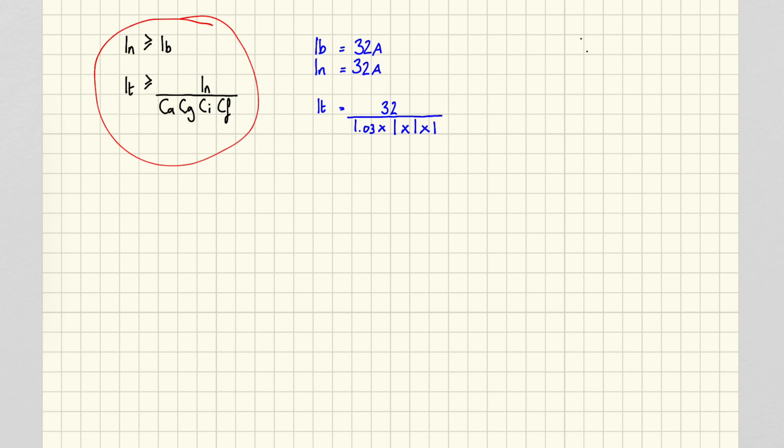The only time really that this factor is taken into consideration is if it is a BS7671 rated 3036 semi-enclosed fuse, which are the old-fashioned put-a-wire-in type fuse connection, and then that one gets a rating factor of 0.725. So it's either a 1 or it could be 0.725. So that's the only time, and that's if it's a semi-enclosed fuse.